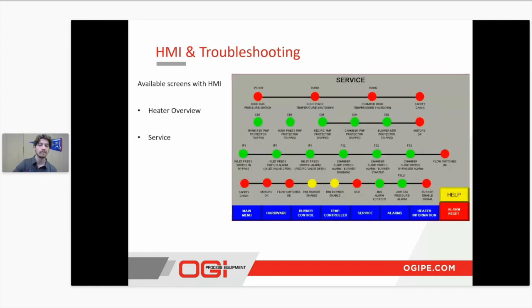Next, we have our service screen. So you can see here, if there's anything red, there's going to be an issue with it. It's very easy to come in here, check this, and diagnose what is going on with your heater. So as shown here, we currently don't have the HMI heater enable and burner enable buttons pressed on that last screen. Therefore, they're yellow. Once those are enabled, those will turn green, as well as all of these safety chains that are currently red.